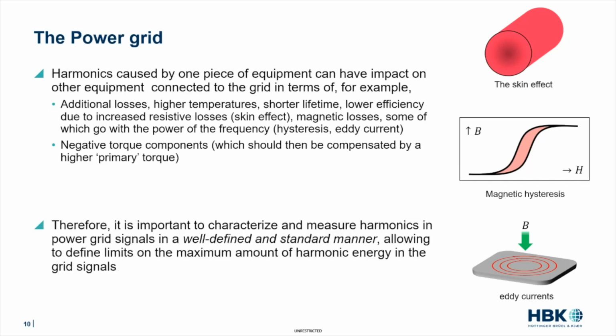Therefore, it is very important to be able to characterize and measure harmonics in power grid signals in a well-defined and standard manner. And why is that necessary? Well, it allows us to define limits on the maximum amount of harmonic energy in grid signals. Harmonics are things that you don't want, but you cannot always avoid them. So it is very useful if you can measure harmonics in a standardized way, and then, for example, certain institutes can say, okay, this device is acceptable to be sold because the harmonics that it generates on the power grid are below a certain level. So that is very important.